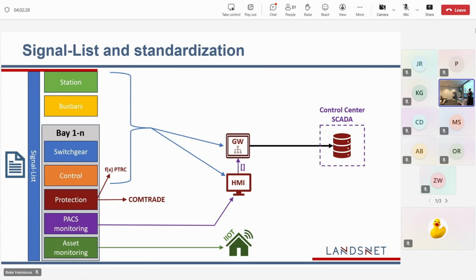Same with, we are always rethinking about the PACS monitoring, if it should always come from the source, or if the HMI or something should look at it holistically and then give some group alarms up to the dispatch. And for the protections, again, we put everything in a COMTRADE file because we have a system to automatically fetch those and even do disturbance analysis. But we'd rather take the general trips or the PTRC for each protection rather than having to define every single one.